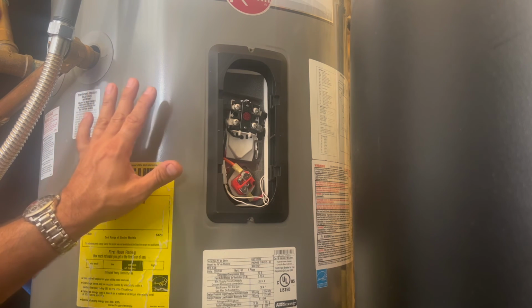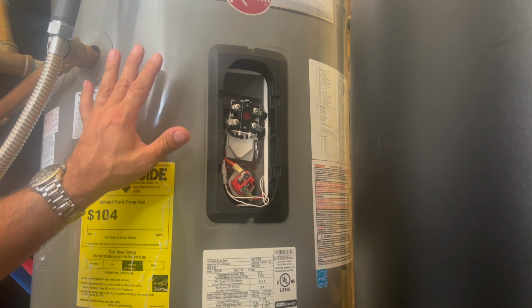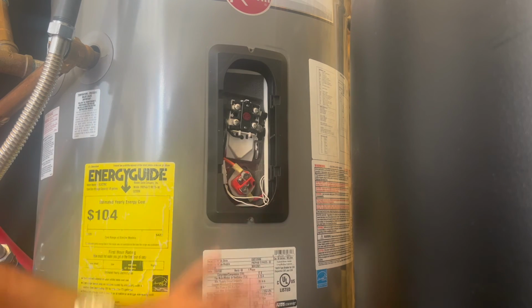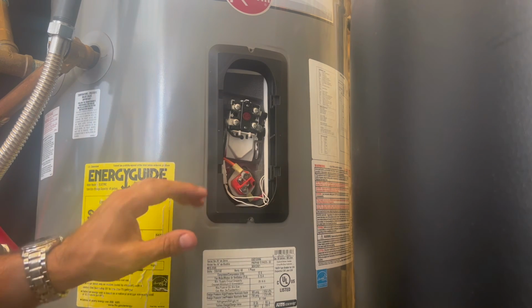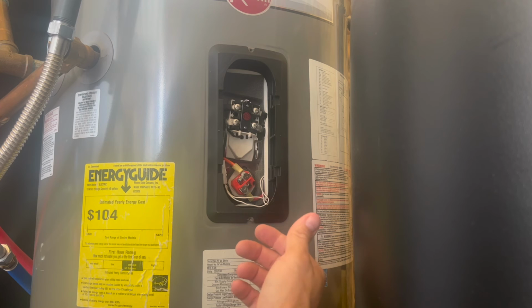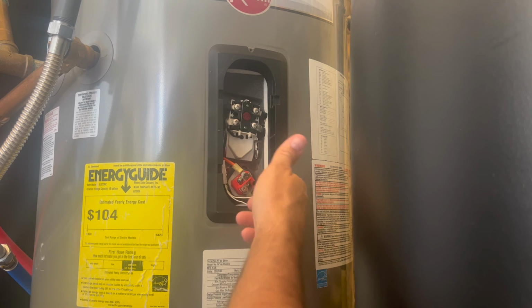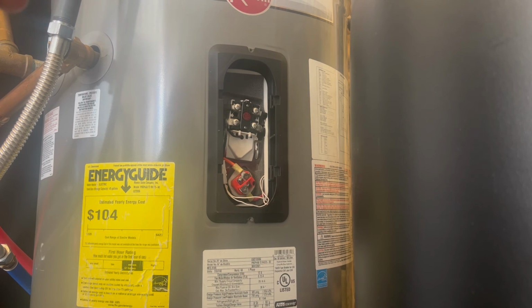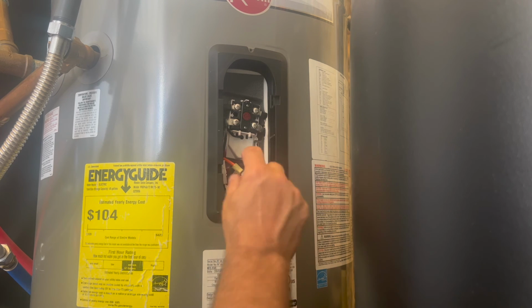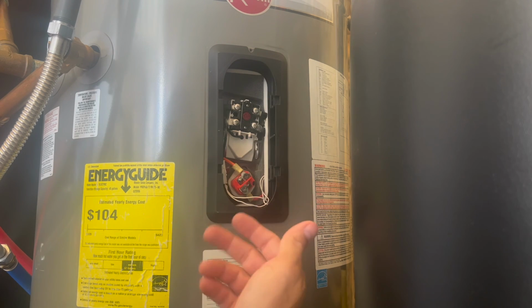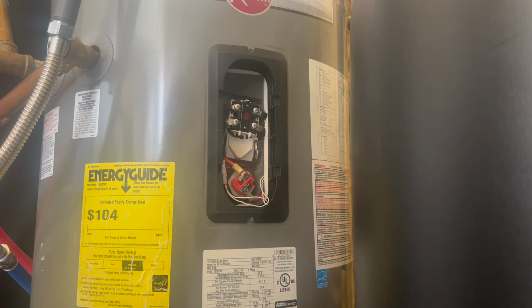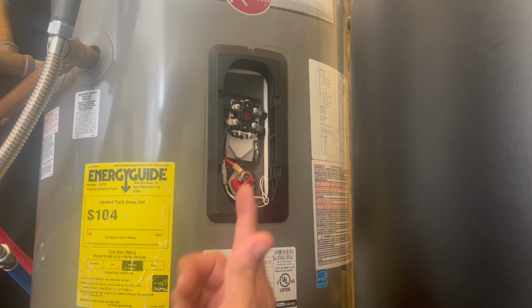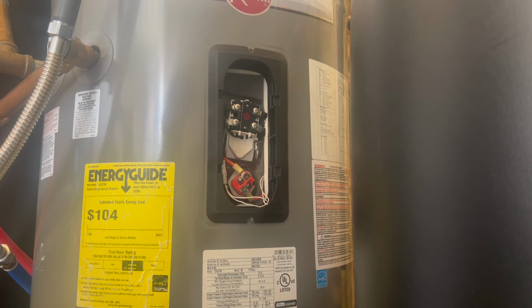and that's basically temperatures. Okay, I've seen instances where not so much down here, elements will sometimes be grounded or blown, and that's in another video we have where you can see how to test an element by disconnecting power and removing the screws, and then you use the ohm meter to ohm it out and make sure that you've got good continuity and good resistance through the element. But on the thermistors up top, you'll see the system running. You might see some weird temperature.